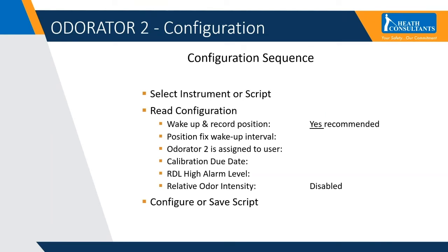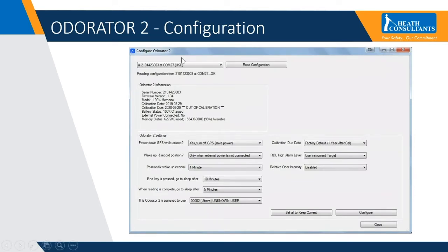So once in configuration, the sequence to bring it in and also change it is within the window, and I have a window on the next slide. You select either your instrument or a script file that contains the data, and then you read that instrument or that script file, and that brings the existing configuration information into Odor Seer so it can be viewed and modified. Then the respective fields are modified, and then that configuration is either saved locally to the instrument, or if a script was brought in, then you have the option of saving a new script to record the changes, for future use. So this is an image of the configuration page within Odor Seer.